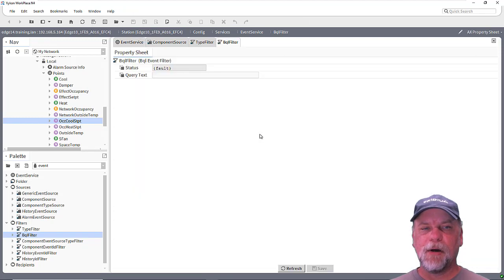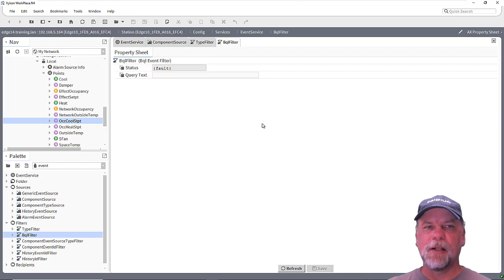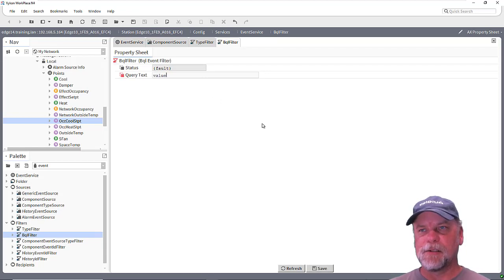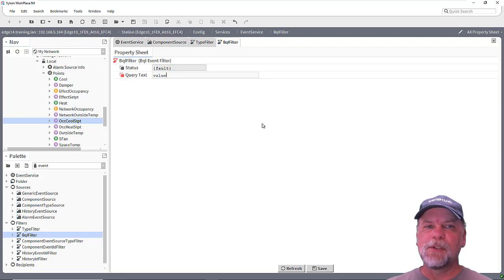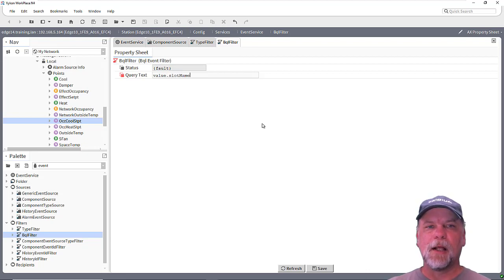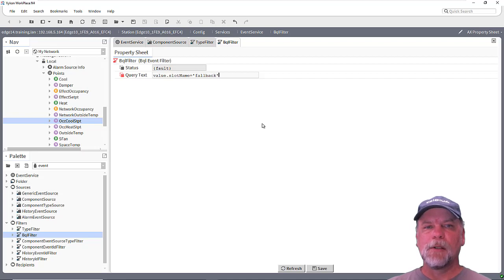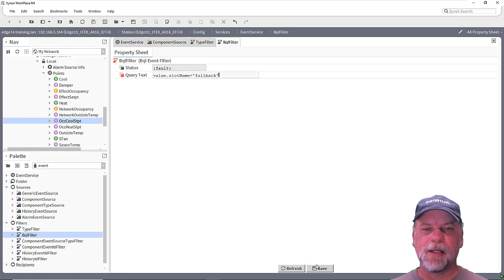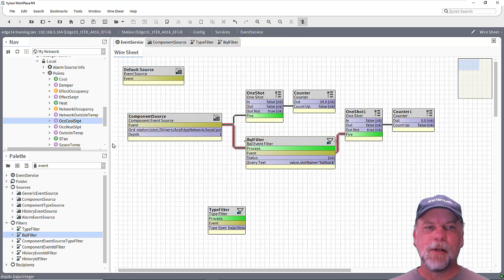Now, looking at the BQL filter, we can get the value from the event just by saying 'value' — it's really get value, but it gets abstracted down to just the word value. And once we get the value, that's the B value that changed, then we can check something about it. Like maybe the slot name equals 'fallback'. Each control point, when we invoke the set action, that actually changes the fallback slot value.